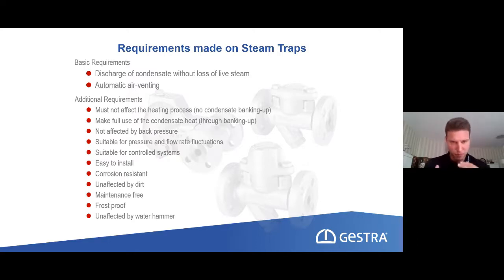The first one is to discharge the condensate without the loss of live steam. We had to use fuel, or we had to burn fuel, to create our steam. This fuel can be very different. We could have oil or gas, or we could have biomass or electric heating rods. It depends. But that tells us, okay, I had to use something that cost me money to create my steam. And this makes steam have a price. And if I just put this steam through a steam trap without making use of it, I'm losing quite a lot of money. So this is a very basic thing that we really have to guarantee. We have to discharge only the condensate without a loss of live steam.